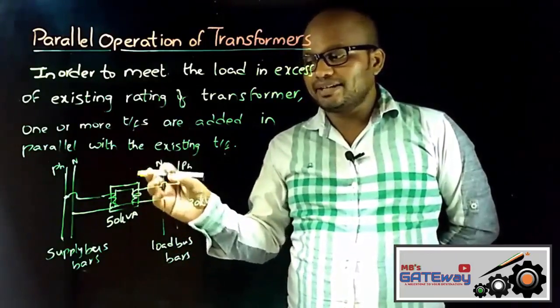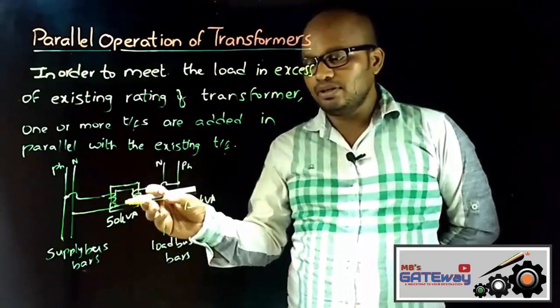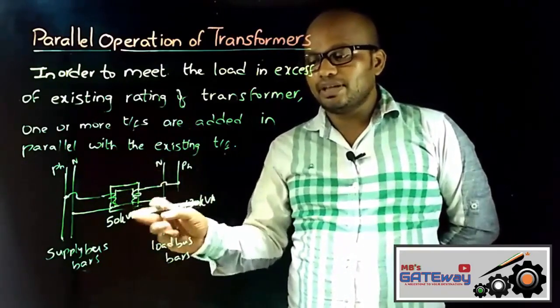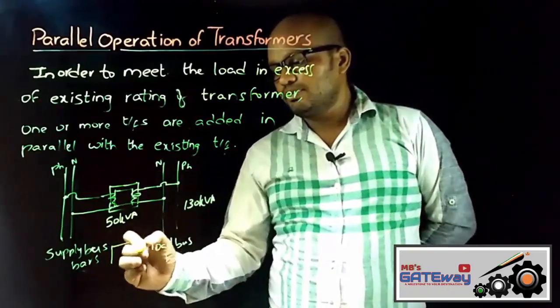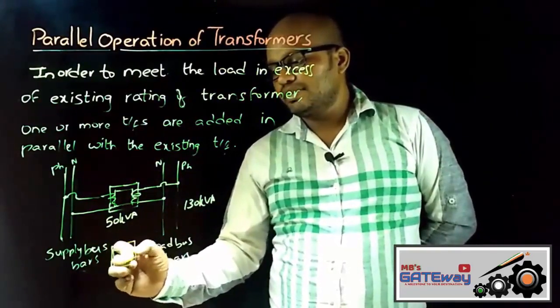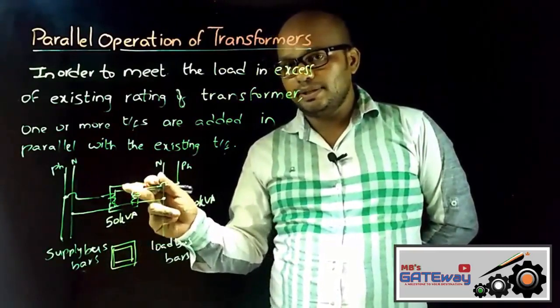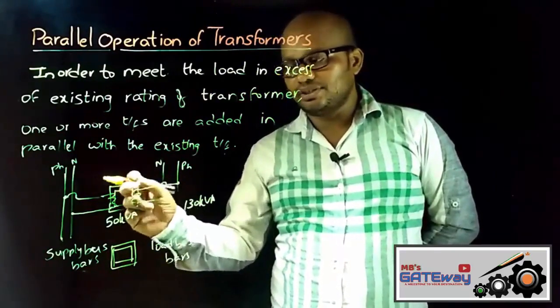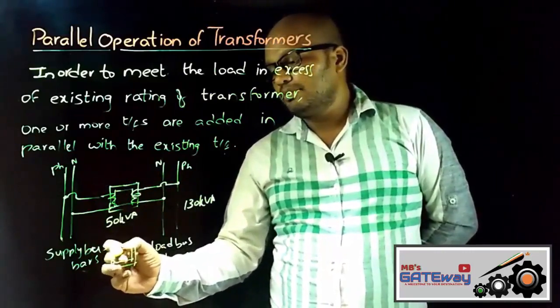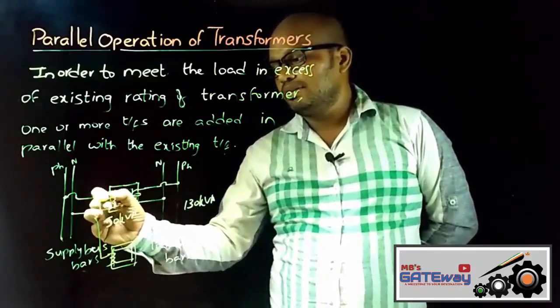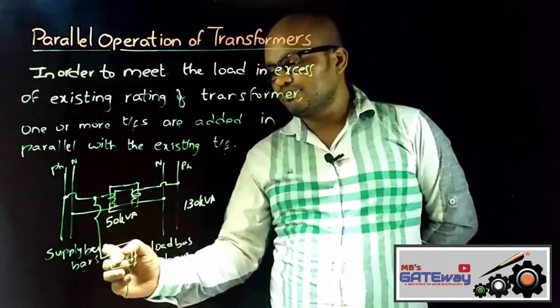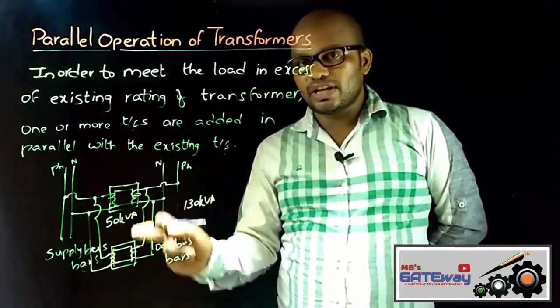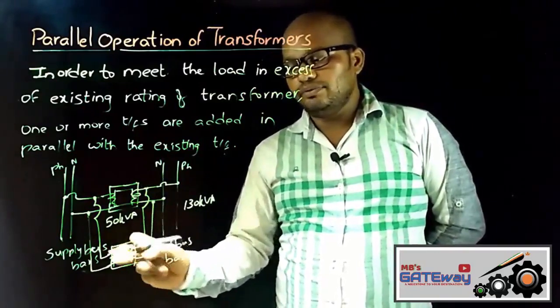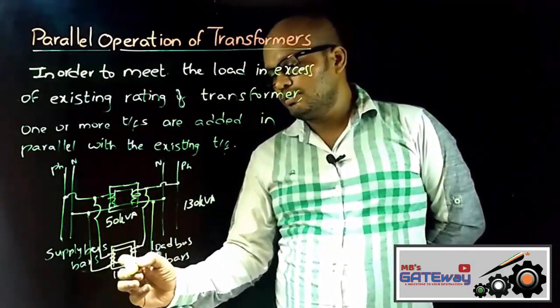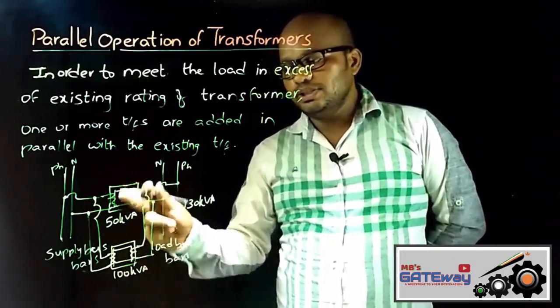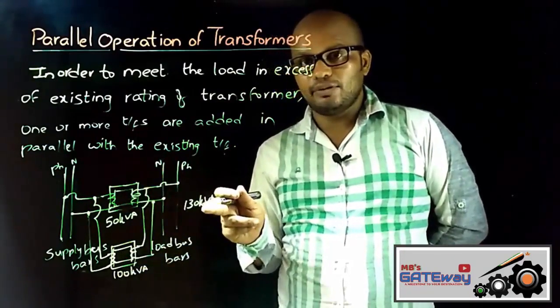We must add a transformer in parallel with the existing transformer such that both transformers will supply this load. So let us suppose this is the additional transformer which we are connecting in parallel with the existing transformer. The primary windings are connected in parallel with the existing transformer like this. Now this represents two transformers operating in parallel, and if the additional transformer rating is, let us suppose, 100 kVA, these two transformers together can supply the required power to the load.